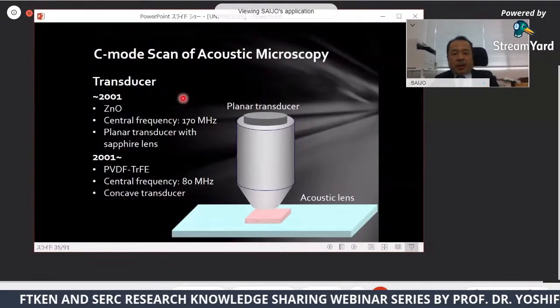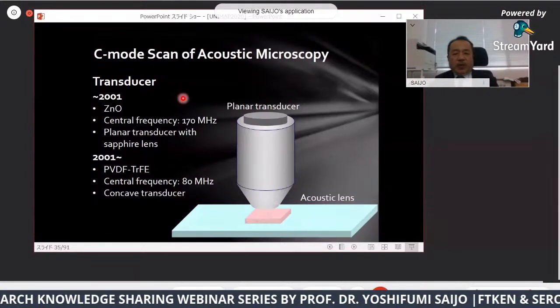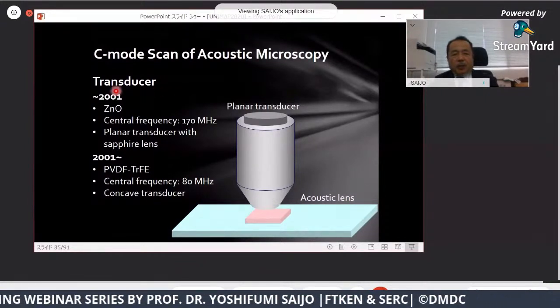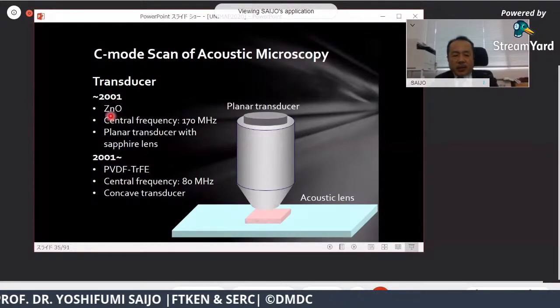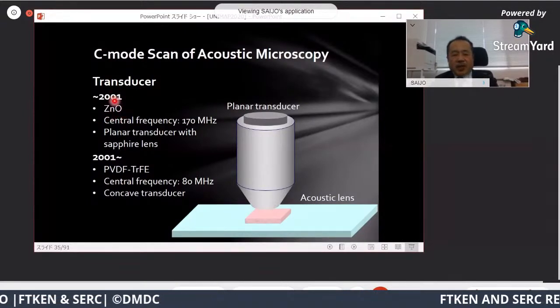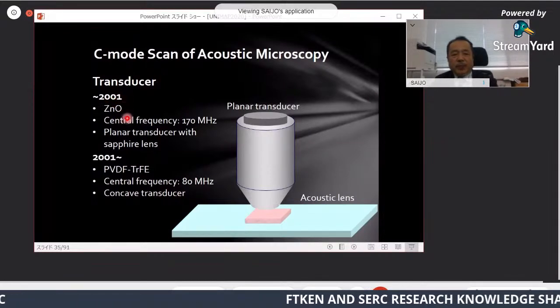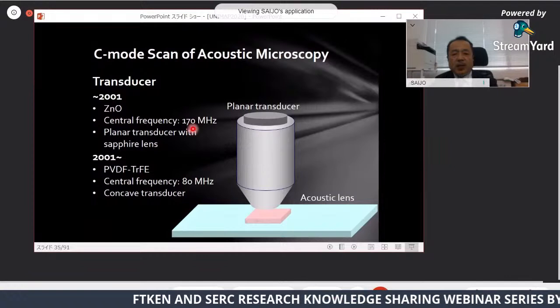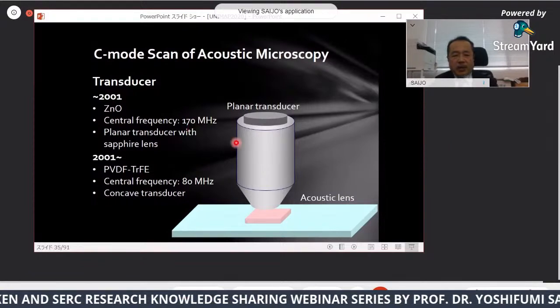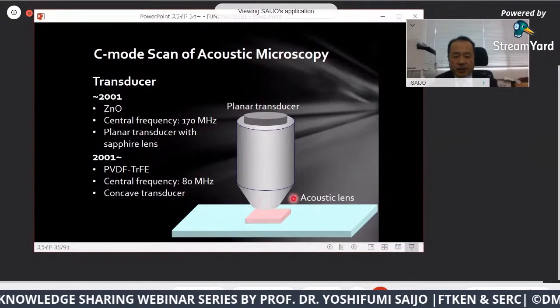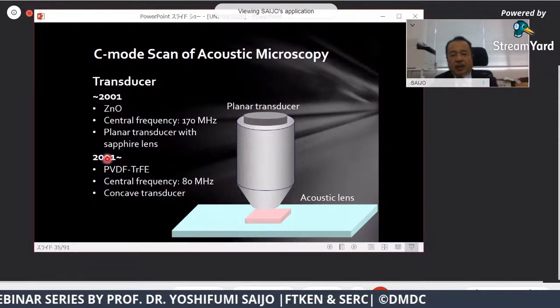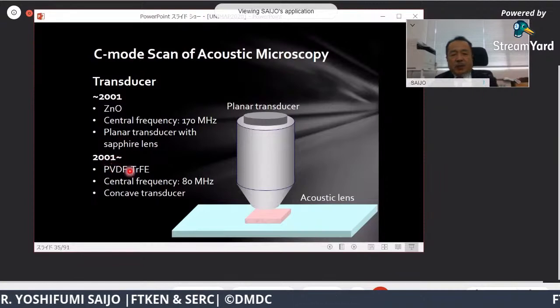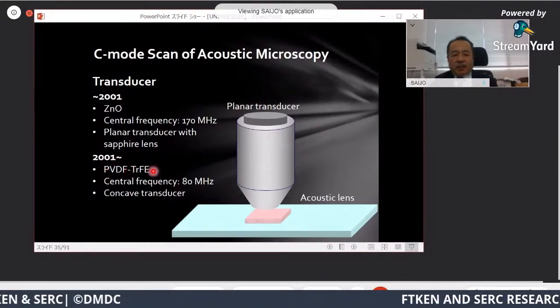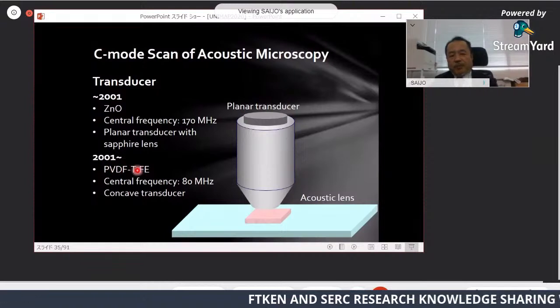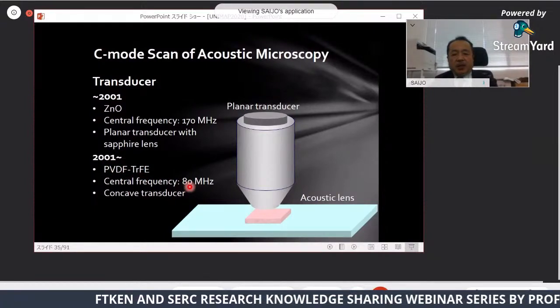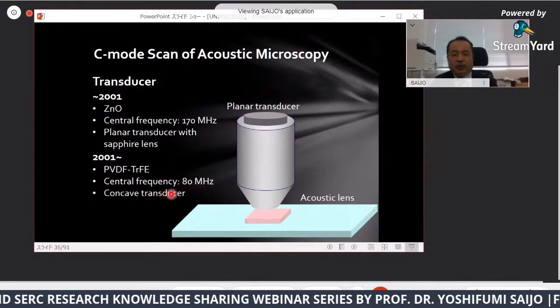And now I will introduce what is the acoustic microscope. Actually, we used zinc oxide as the transducer material from 1980 to 2001. And the central frequency was 170 megahertz. And that is a planar transducer with a sapphire lens, acoustic lens. And after 2001, the material changed to PVDF-TrFE. This is a film. And the central frequency is 80 megahertz, and we use the concave transducer.